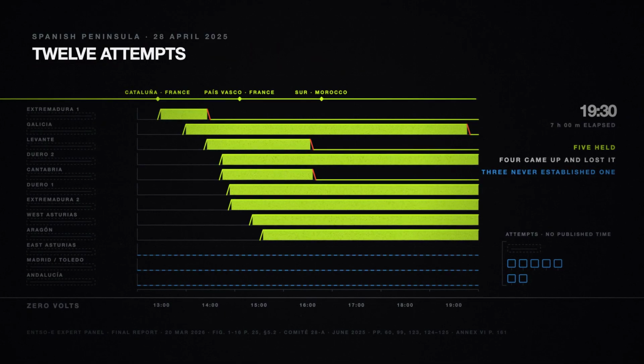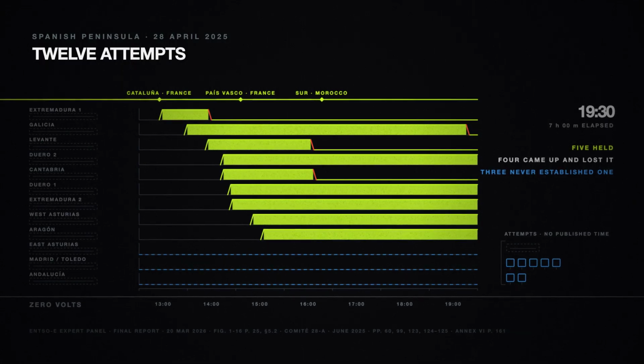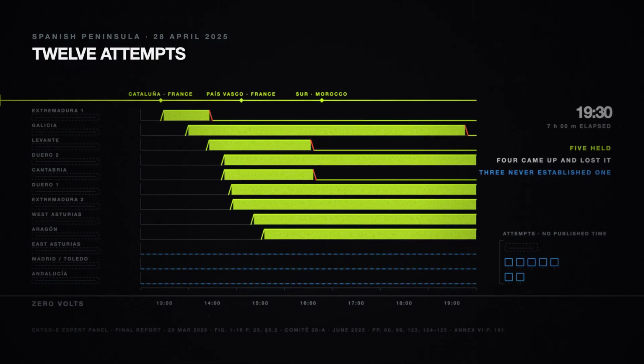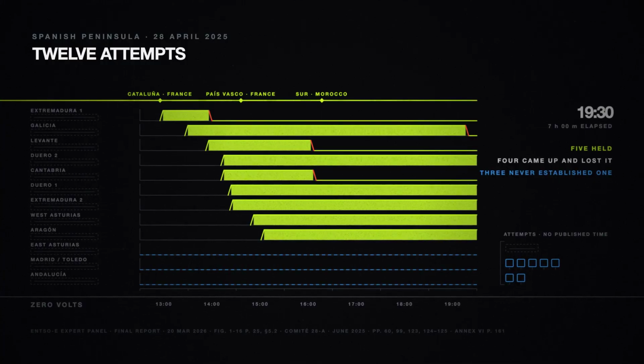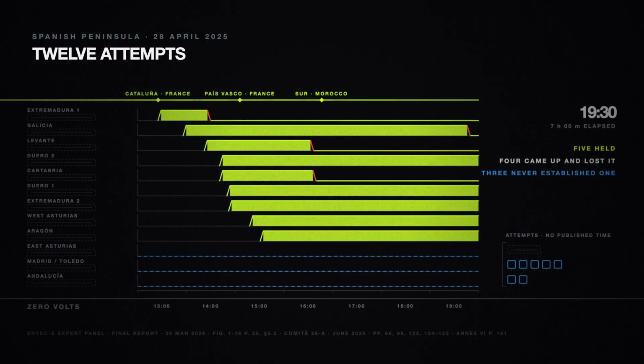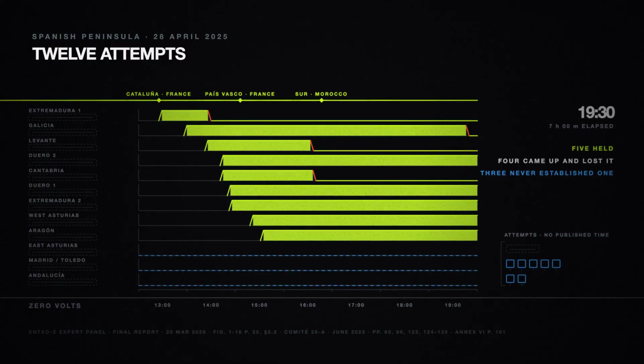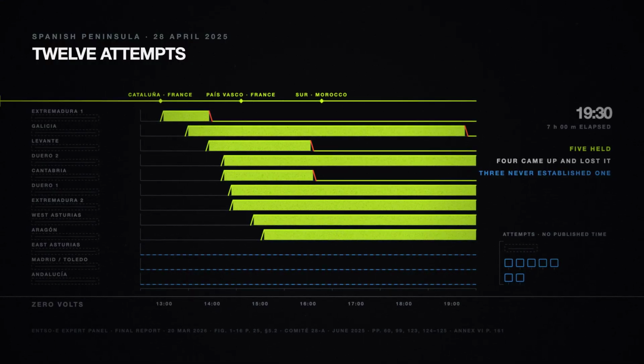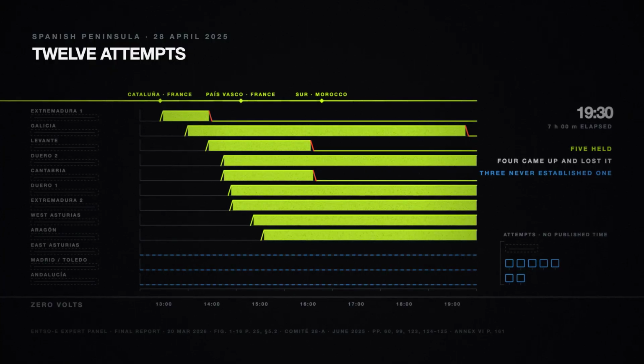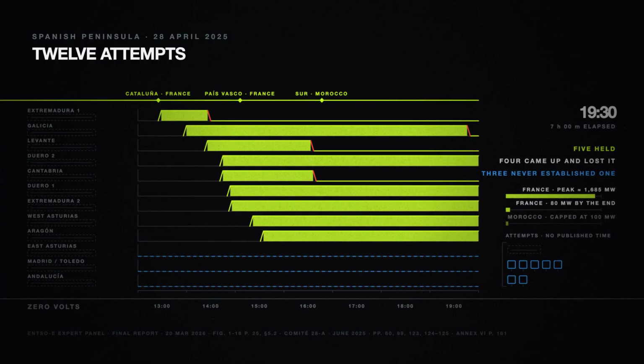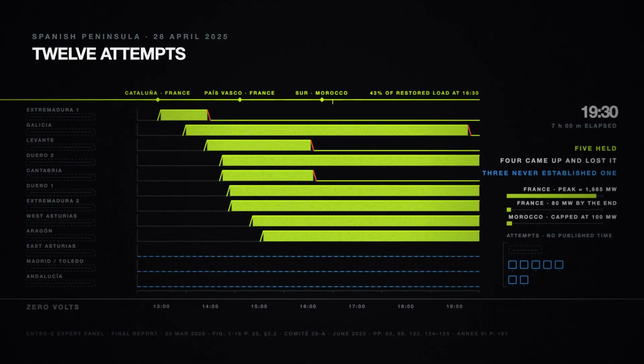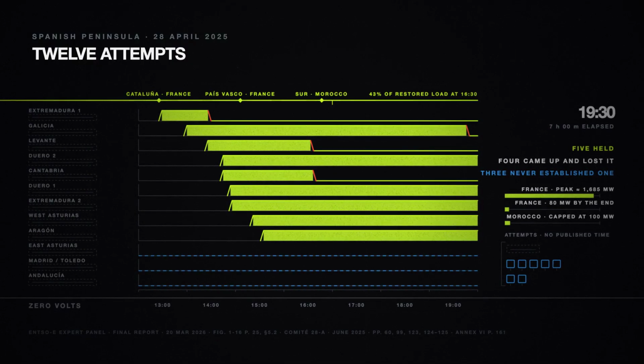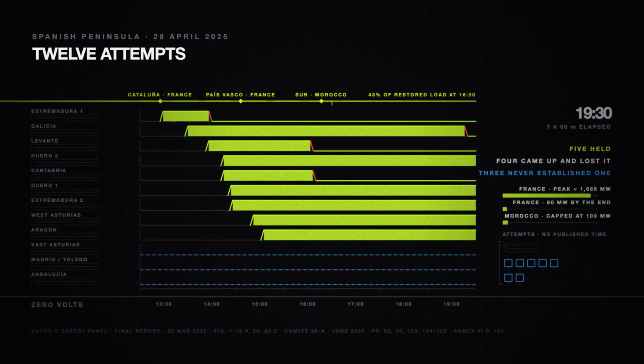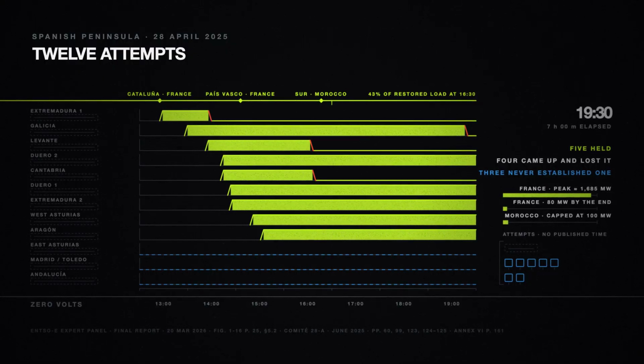The restoration was based on 3 main islands, Catalonia and the Basque Country with support from France, and the south with support from Morocco. "The prompt supply of voltage and energy from France and Morocco," the committee writes, "allowed the first islands to be raised, islands from which the combined cycle plant's auxiliaries could be fed." As energy it was small, France peaked at about 1,685 megawatts and was down to 80 by the end, and Morocco was capped at 100. As a reference, it was decisive.